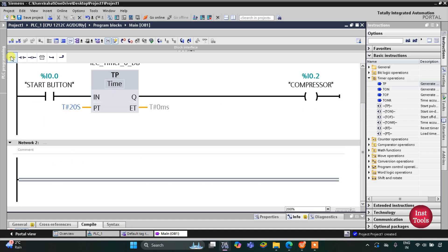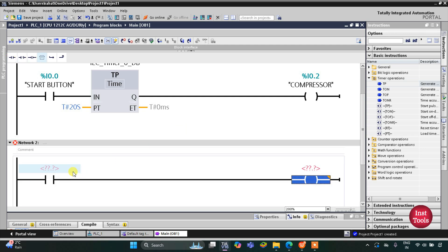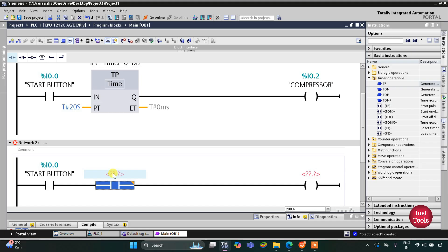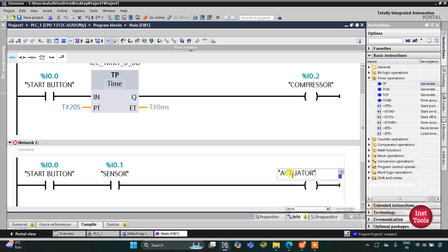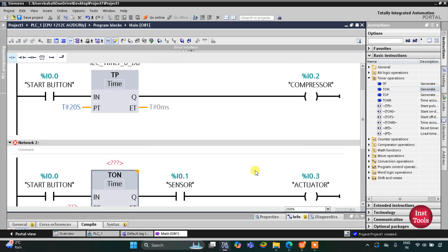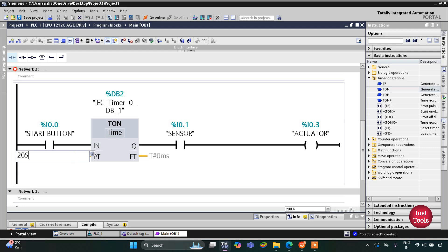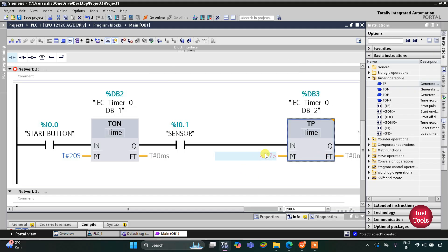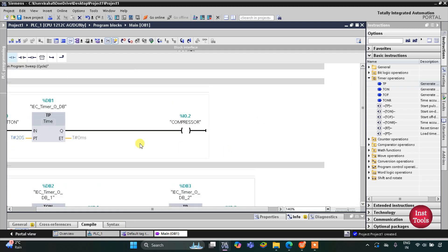In Network 2, I will insert a normally open contact for the start button, then one more normally open contact for the sensor representing the trash collecting tray, and a coil for the actuator. The actuator will run after the compressor stops, so there will be a 20-second delay using a TON timer with a preset of 20 seconds. The actuator will throw out the trash for 10 seconds, so I will use a TP timer with a preset value of 10 seconds.